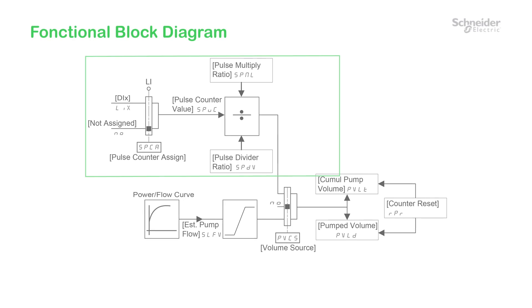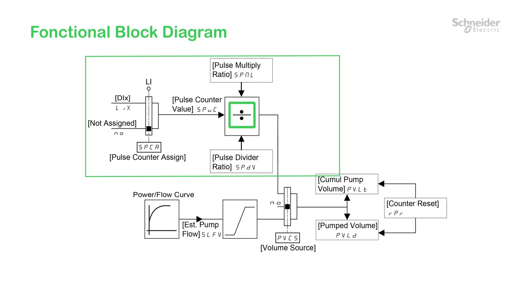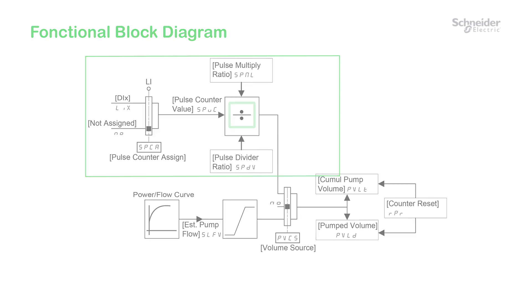The pulse counter value is converted into volume with a resolution of 0.1 liter per pulse using the two ratio parameters: Pulse Multiply Ratio and Pulse Divider Ratio.